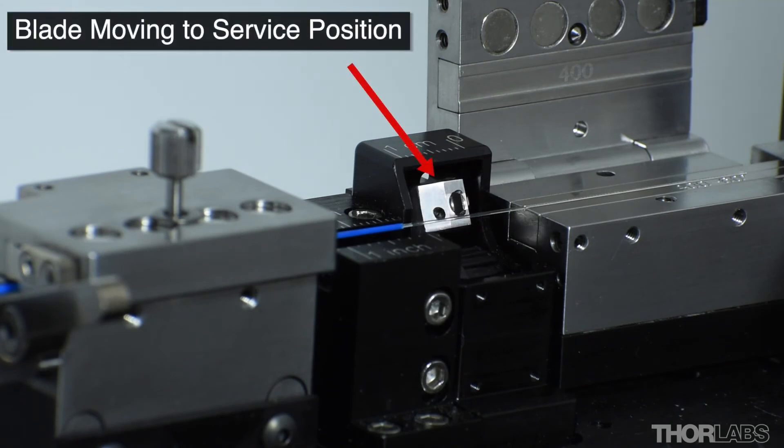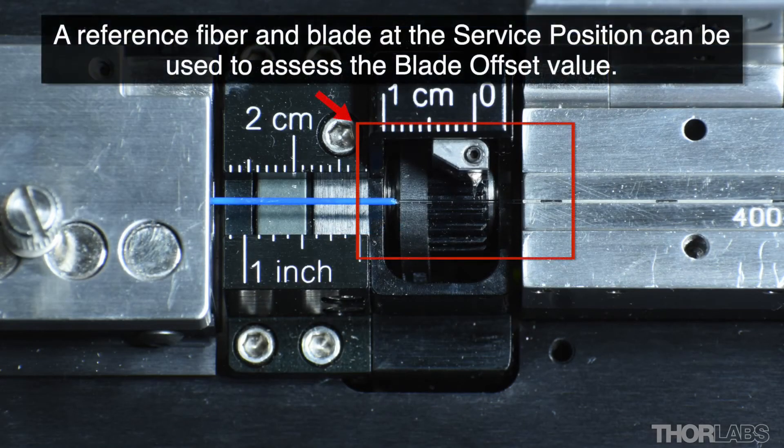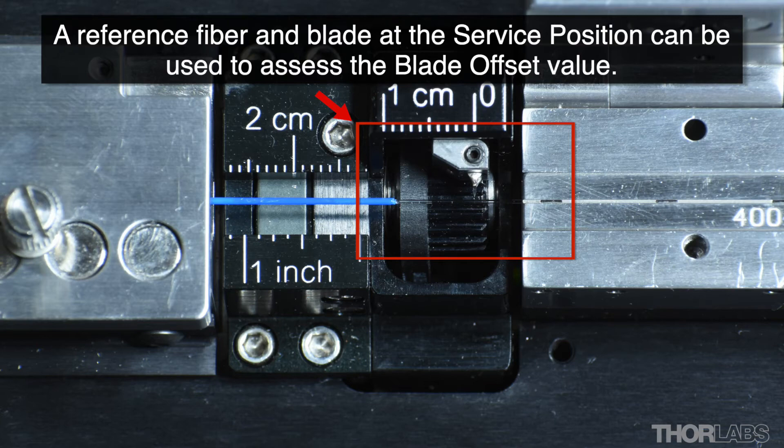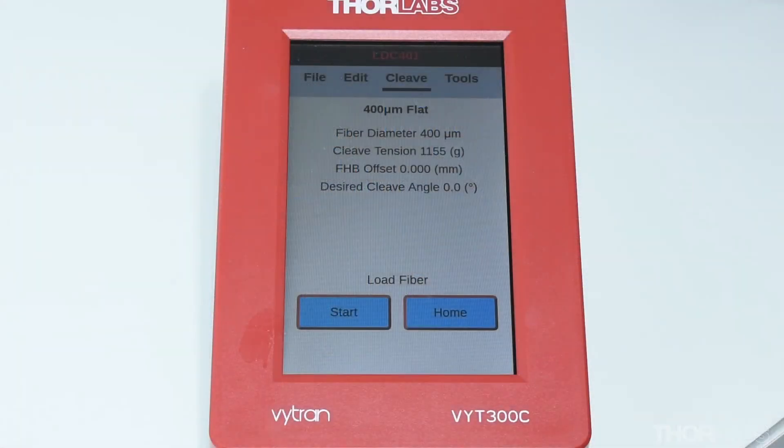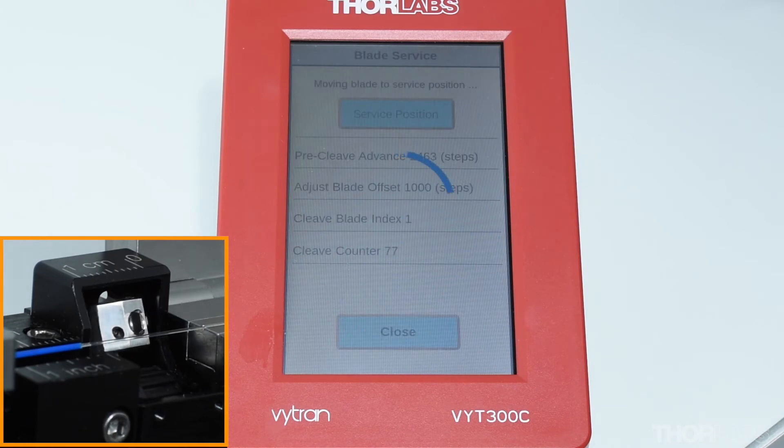When the cleave blade is moved to the service position, it moves forwards by the blade offset plus the pre-cleave advance distances. In other words, the same as the blade's initial forward move at the start of a cleave. Moving the blade to the service position with the reference fiber in place can be used to judge if the blade offset value is set correctly. With the reference fiber in place, use the handset to move the blade to the service position. Once the move has completed, observe the blade's end position relative to the reference fiber.